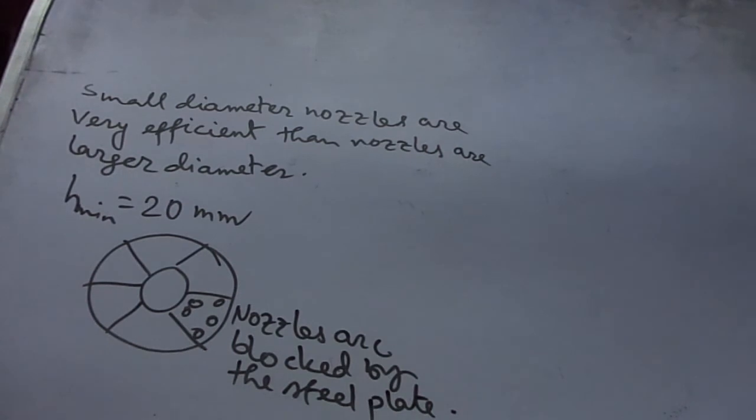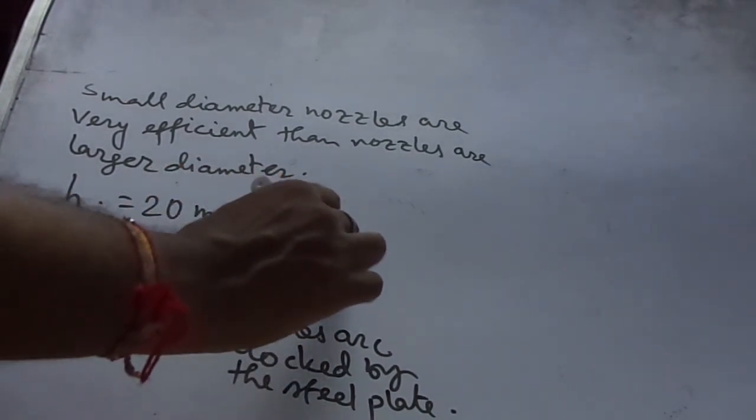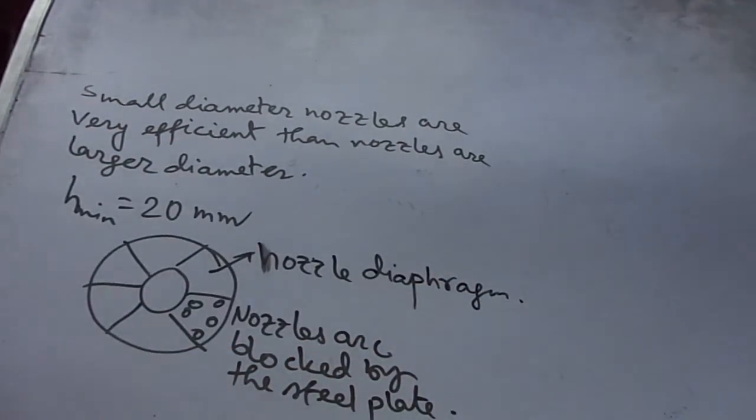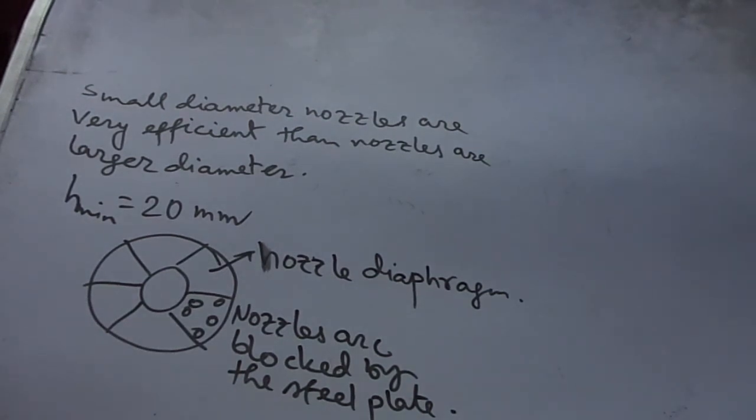And another one is the nozzle diaphragm. Thus, by increasing the estimated Hn to its minimum practicable value and simultaneously blocking part of the periphery of the nozzle diaphragm, the flow area An for a certain mass flow of steam at the given condition is obtained.